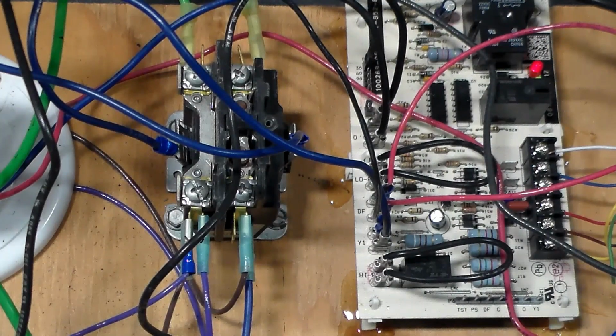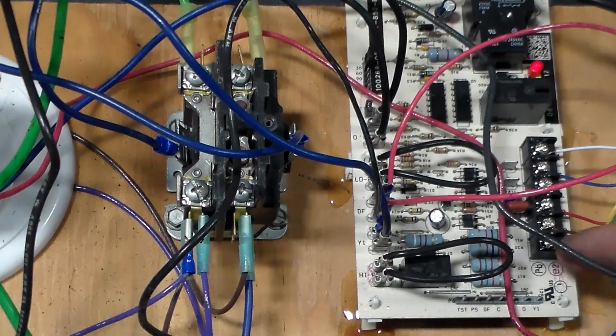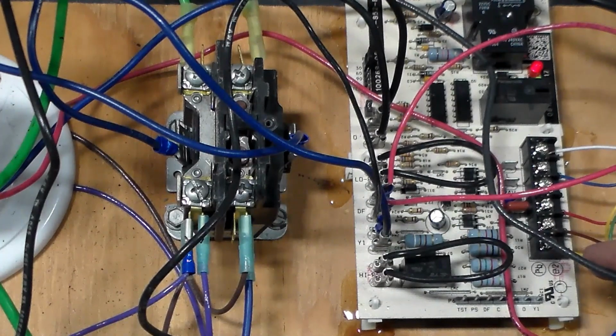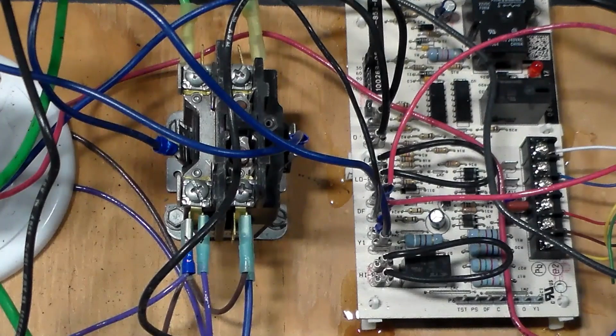But I'm going to start over on the right side with thermostat terminals. And thermostat terminals aren't anything weird than what we're used to seeing on maybe, say, a standard thermostat, right? We have Y1, which we'd imagine would be, you know, yellow, your call for, in this case, it's a heat pump, so I'm not going to say that's the call for cooling. I'm going to say that's the call for the contactor. And we'll see why here in a minute.